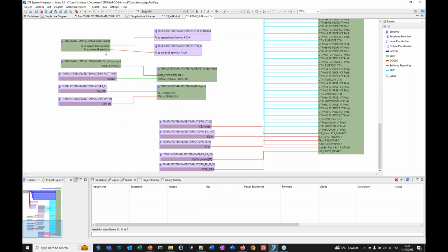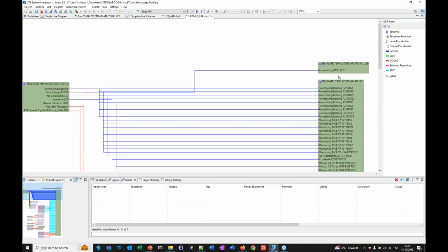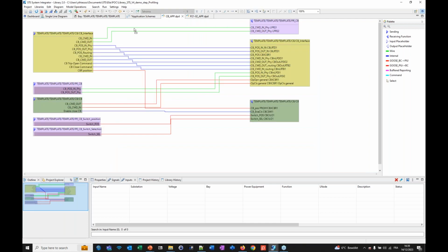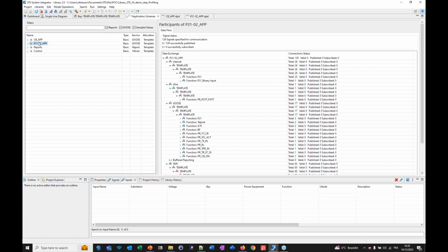We have another process resource on the bottom, which gives the operation close general signal, sent in this case by the PIU, which handles the breaker, to the protection IED. As soon as you have defined the exchange like this, you can then export the file.